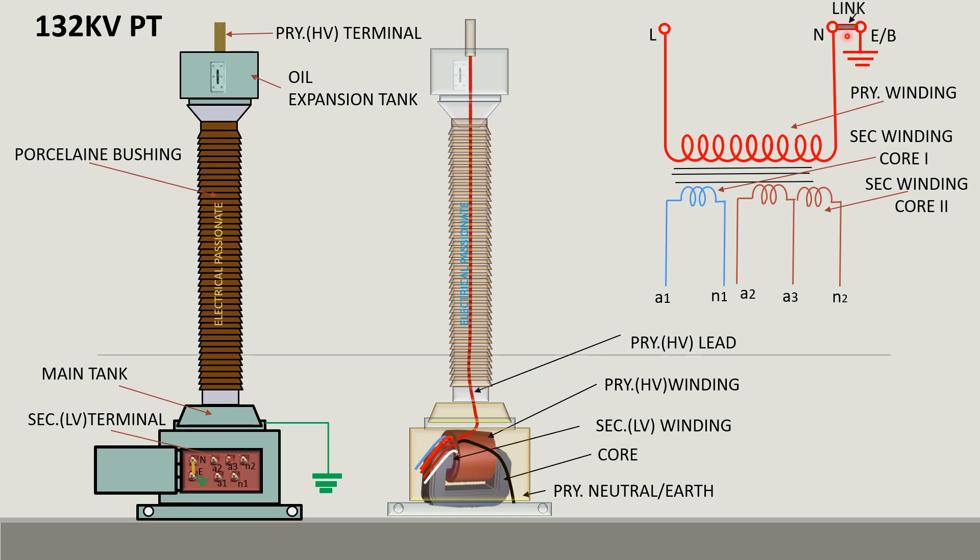While meggering insulation resistance it should be remembered that the said link must be removed. The secondary terminals are drawn outside by suitable insulated bushing. The whole assembly winding and core are dipped into transformer oil, the insulated oil.